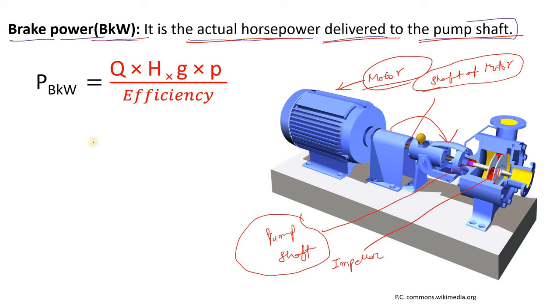So BKW is nothing but the actual horsepower or actual power which is delivered to the pump shaft by the shaft of the motor when your motor starts. Now, how is it calculated? The formula is: P_BKW = (Q × H × g × ρ) / efficiency.